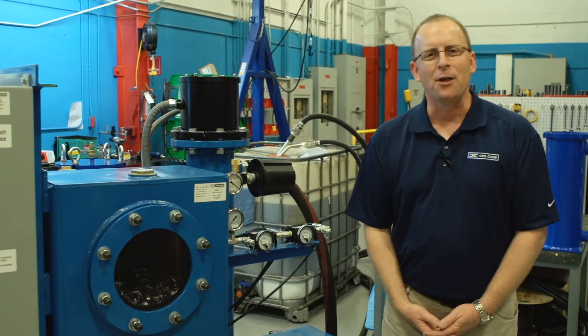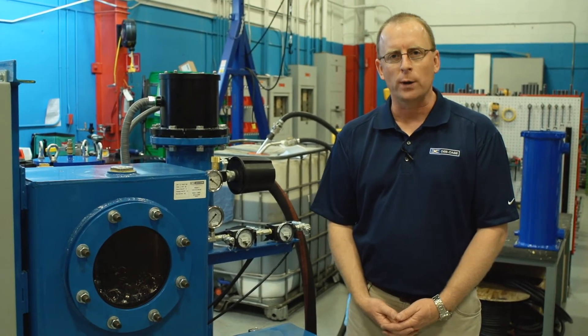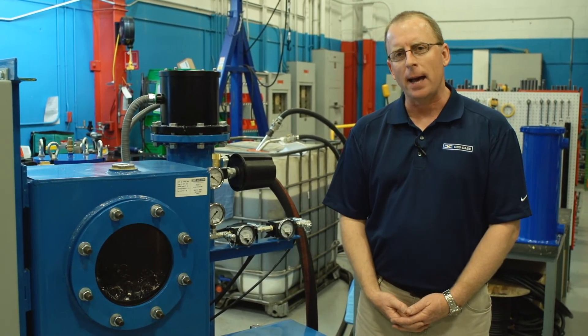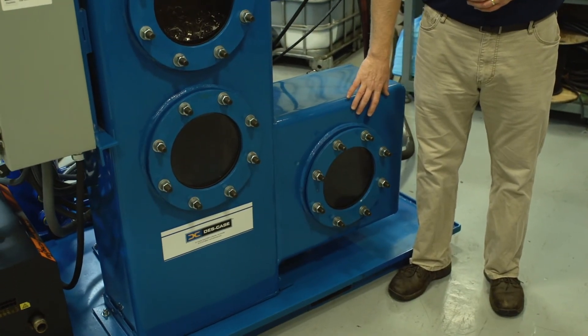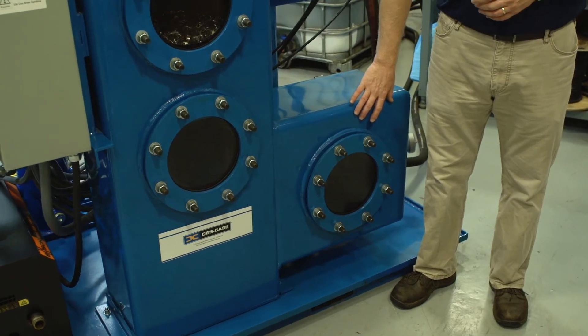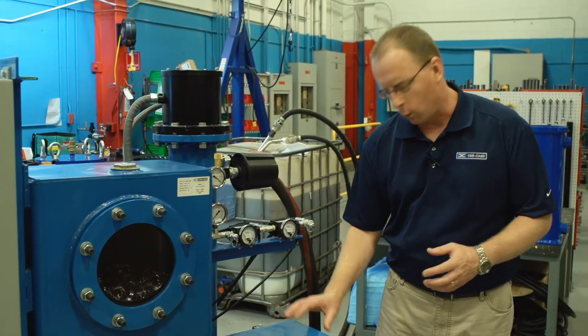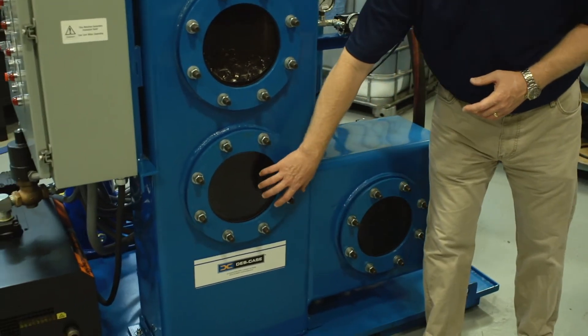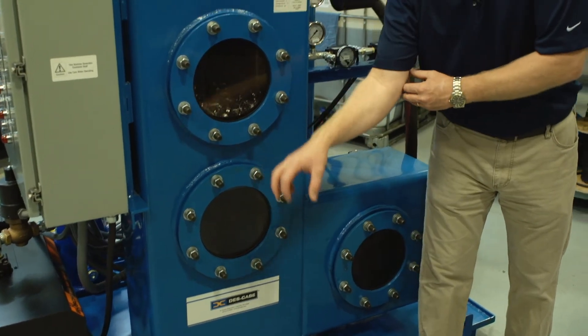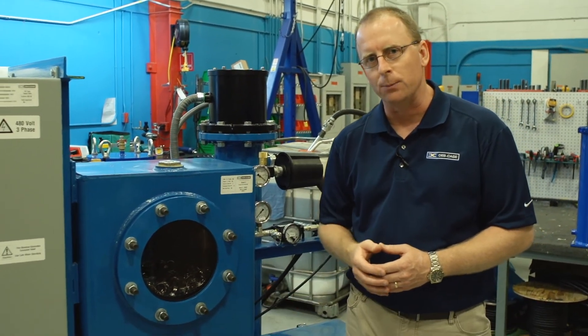The auto drain system allows the unit to run continuously. Another feature of the Des-Case vacuum dehydration system is an automatic flow control system. That automatic flow control system is regulated by a float level globe valve that automatically controls the amount of oil coming into the vacuum chamber. The valve portion is on one side, and on the other side is a float ball that moves up and down, controlling the amount of oil coming into the vacuum chamber.